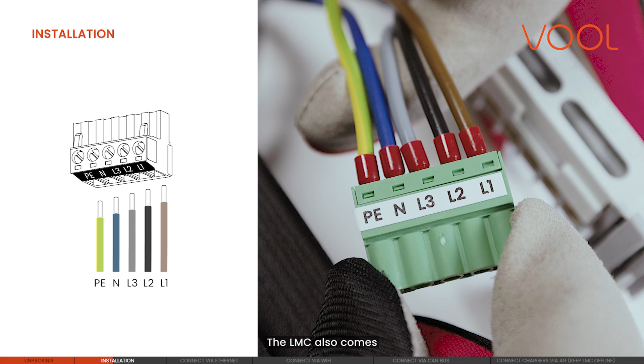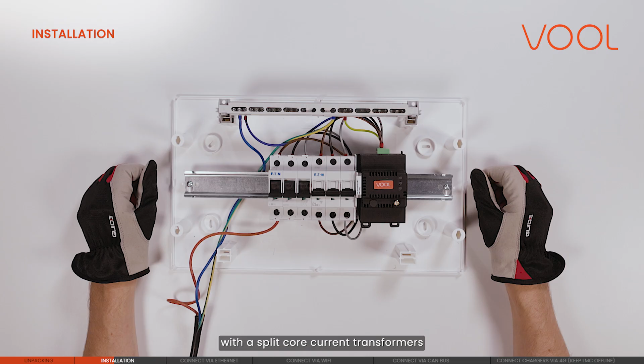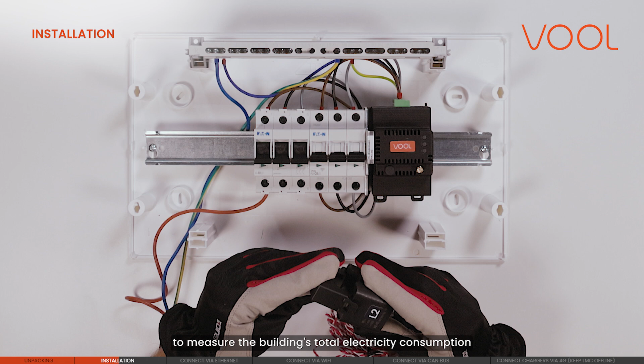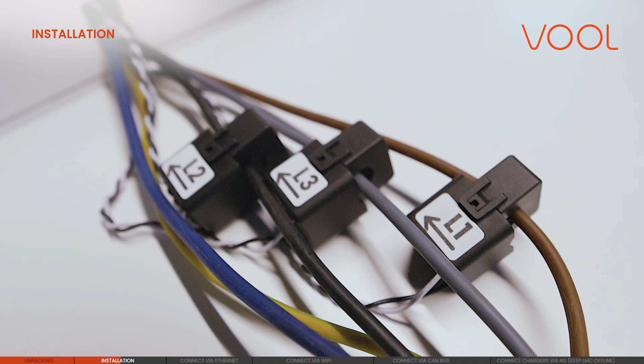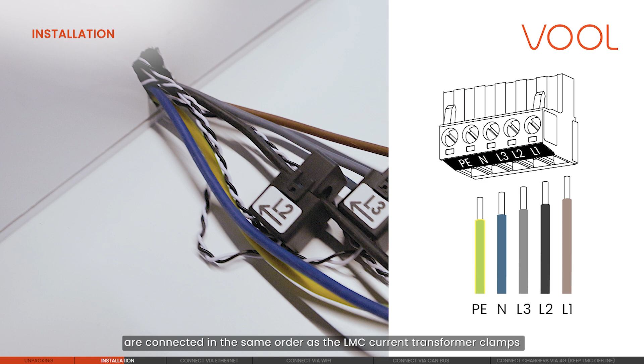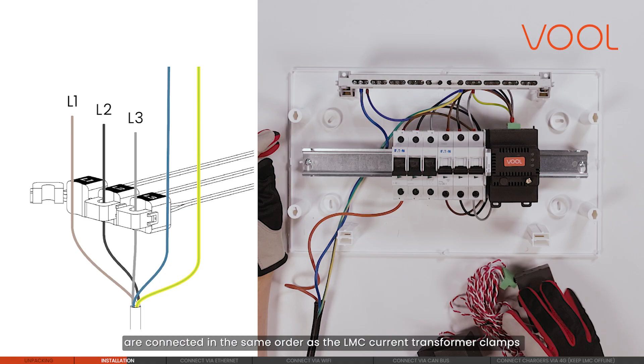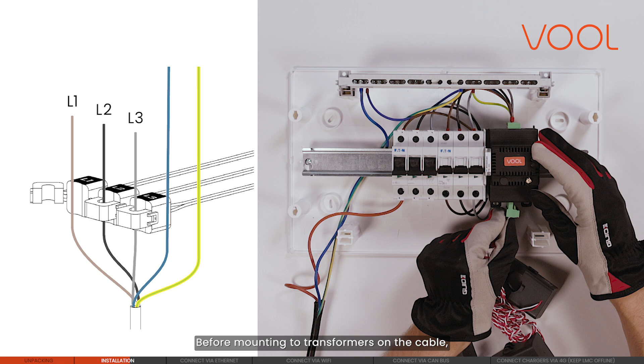The LMC also comes with split-core current transformers. These need to be mounted on your main power line to measure the building's total electricity consumption. Make sure the charger power supply wires are connected in the same order as the LMC current transformer clamps. Before mounting the transformers on the cable, make sure you insert the terminal block into the LMC.